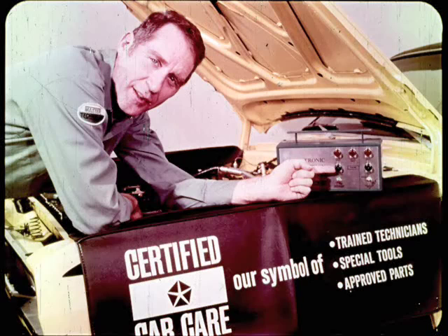Incidentally, the input voltage light must remain on through all tests. If it is not on, the input voltage to the analyzer is not sufficient, and any reading on the light panel cannot be accepted as being accurate.